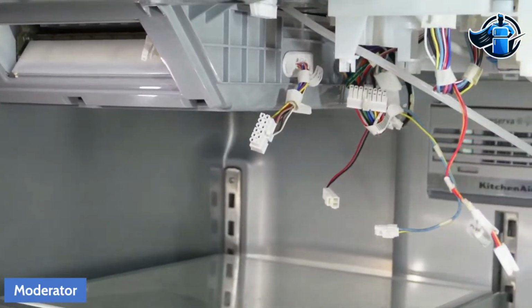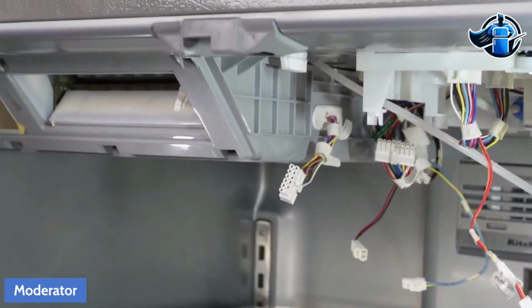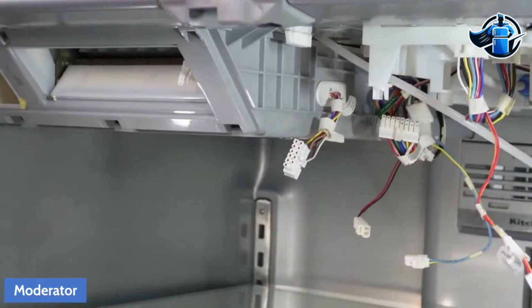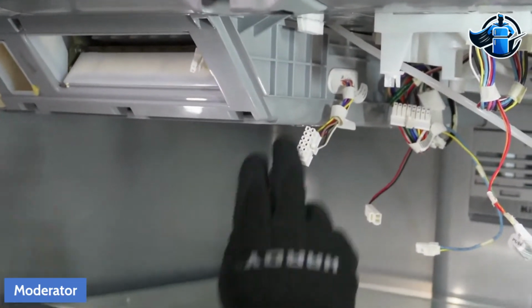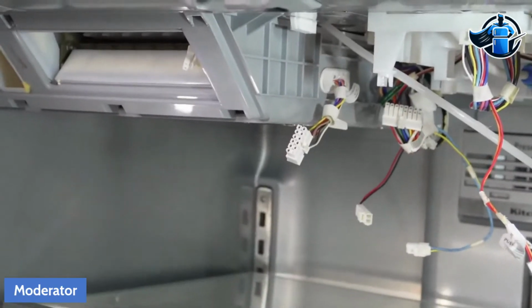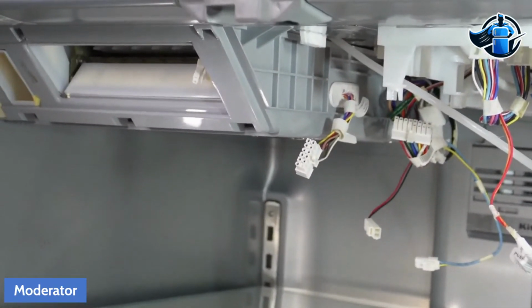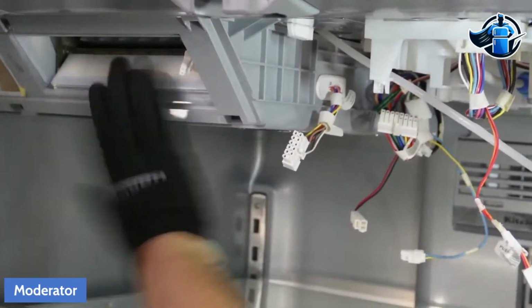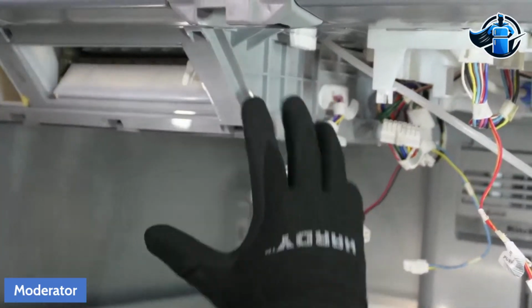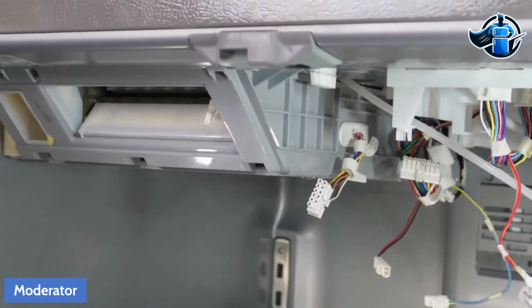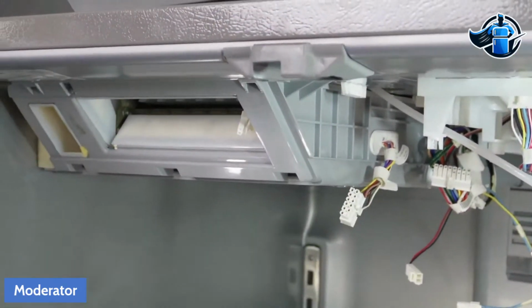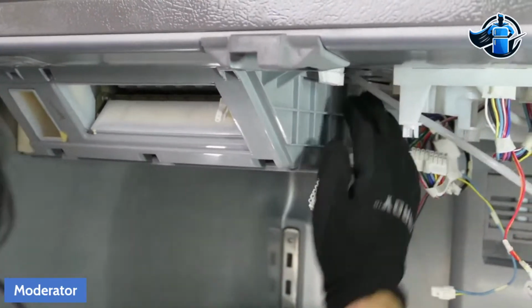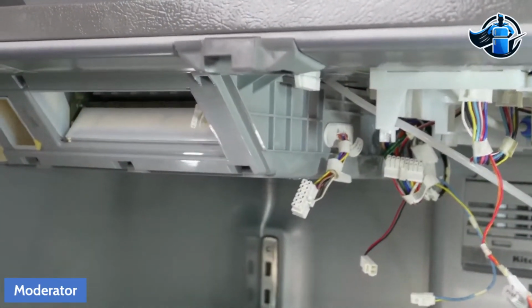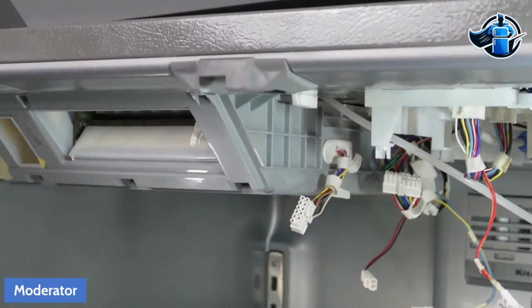It's those two critical steps that, if you miss them, replacing the ice maker and the fill tube heater can still cause the fill tube to freeze again and give you that return call. Every time you service this ice maker or the fill tube heater, layer an extra foil tape over the existing heater and pack this area with Permagum. That's going to prevent you from freezing up again in the future.